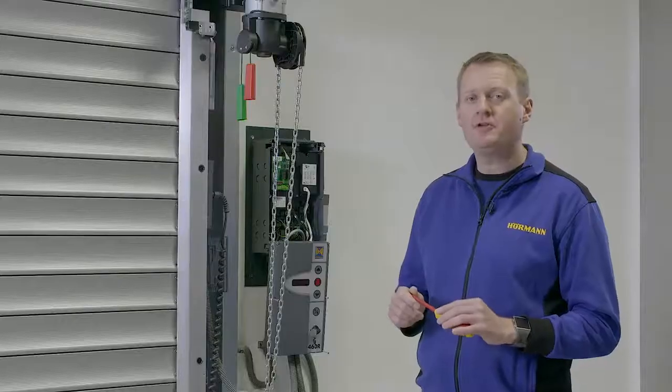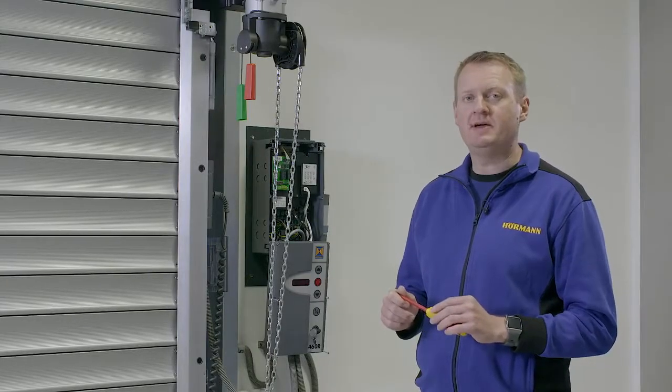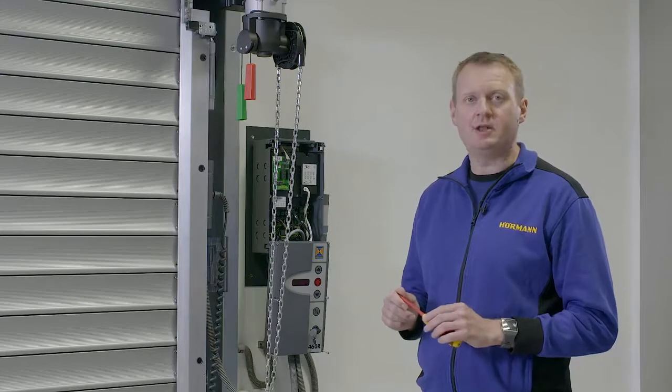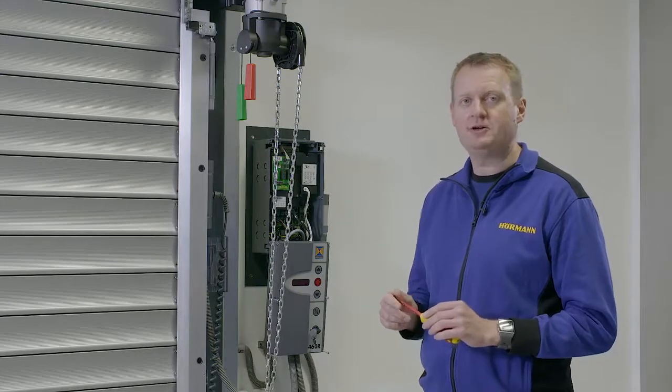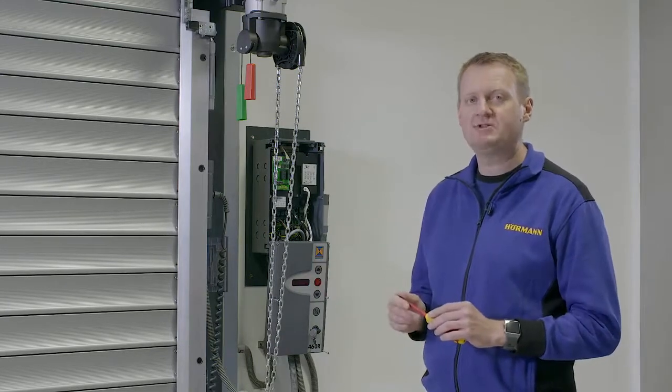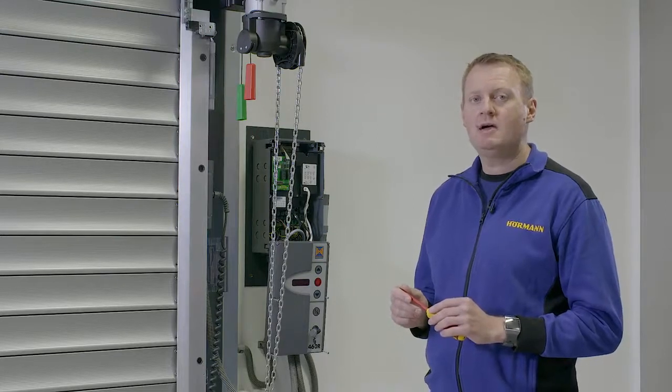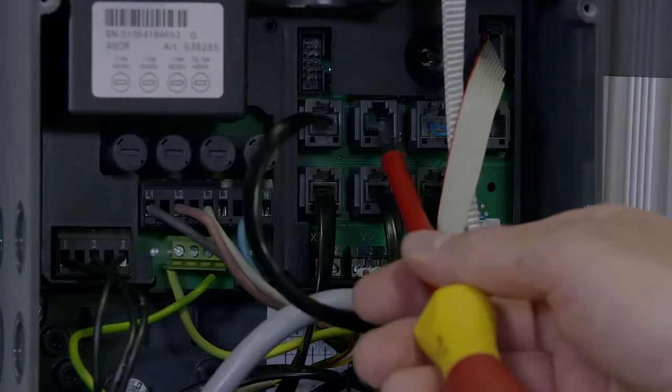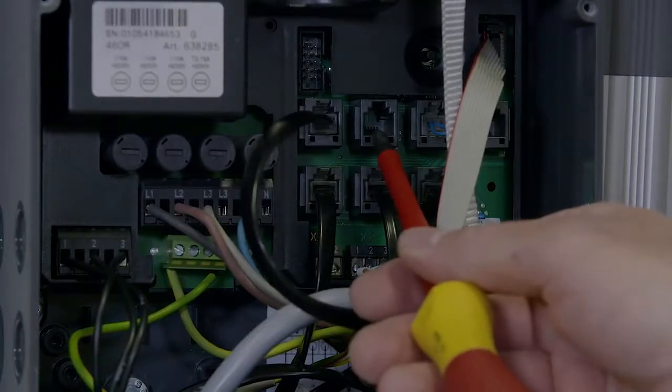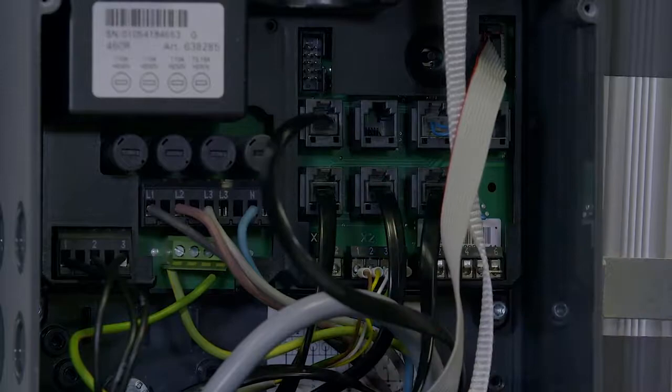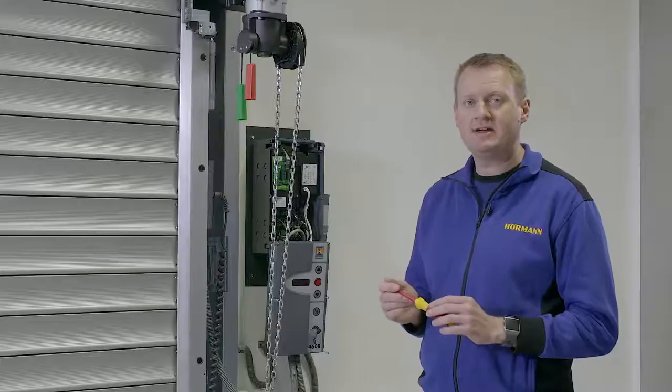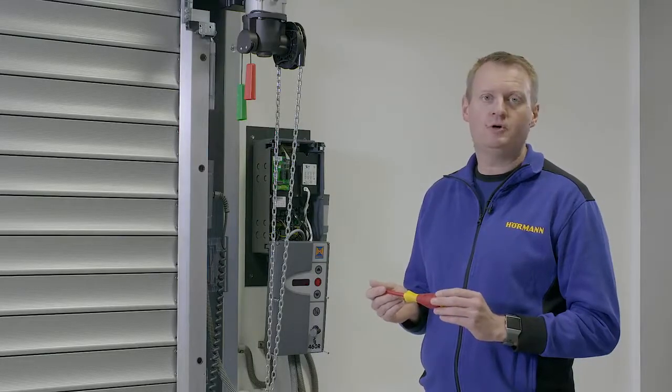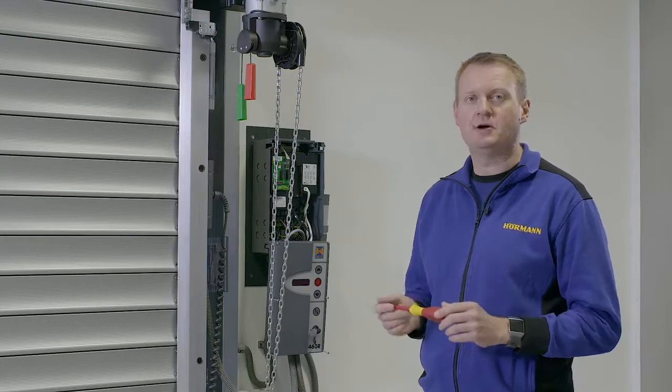If none of the above work, check the type of limits in the motor. Digital limits are plugged into x40 on the control and program 00 is set to 00. If cam limits are in the motor, they're plugged into x42 on the control and program 00 is set to 01. We use this if we're upgrading an old Hörmann control system using the existing motor.